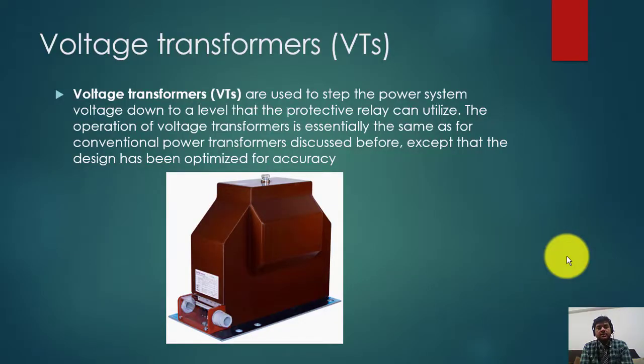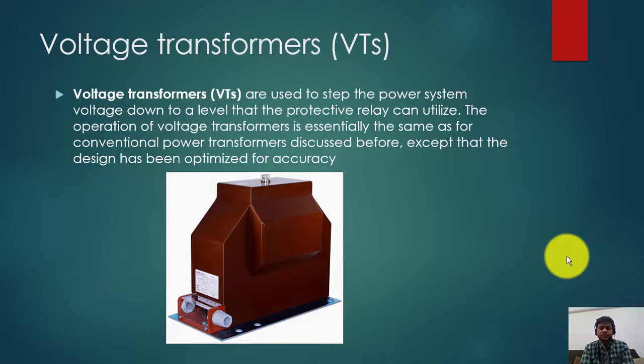Welcome back. Now we will study our next topic, which is the voltage transformer — it's called a PT or potential transformer. We normally use this term in short. In protection engineering, voltage transformers are used to step the power system voltage down to a level that the protection relay can utilize.